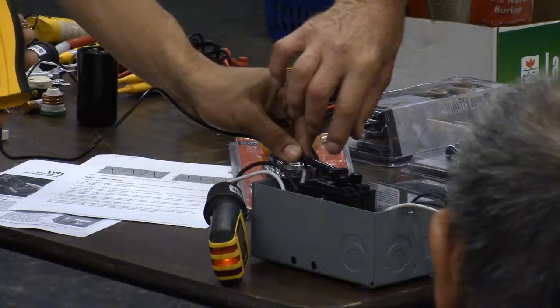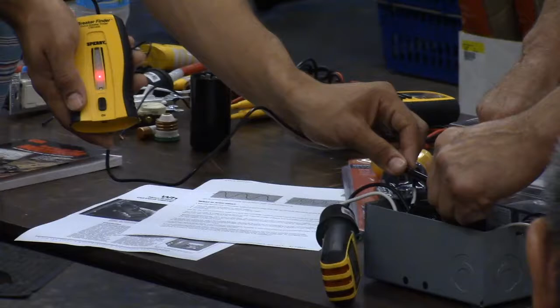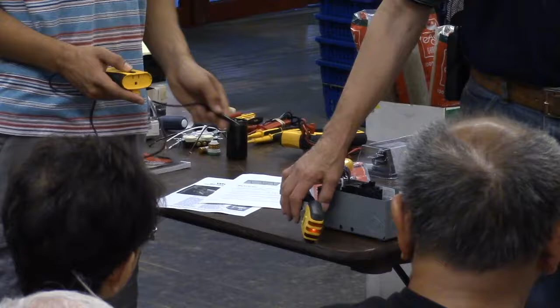Now, what you're noticing is that when he's over here, it's way down, but when he brings it over to the other circuit breaker, it starts beeping. I turn that circuit breaker off, it stops beeping. I know I've just turned off the breaker this was plugged into because it stopped beeping; the light's gone. Verify that, turn it back on, the light comes back on. I've just verified my circuit. So if that's the circuit I want to work on, I can now, with assurance, shut it off at the breaker box. He's just identified that this is in fact the circuit, and not the other one, with the breaker finder.